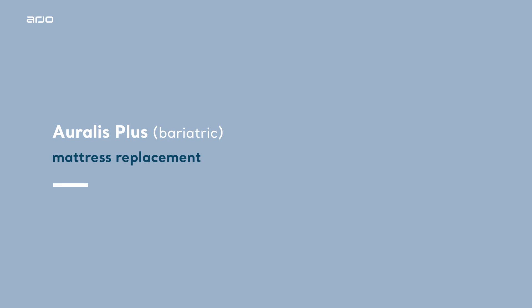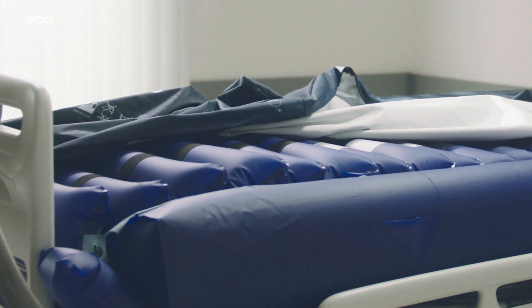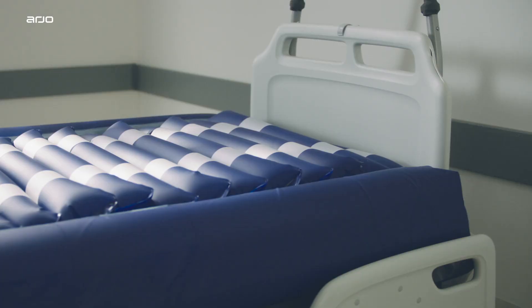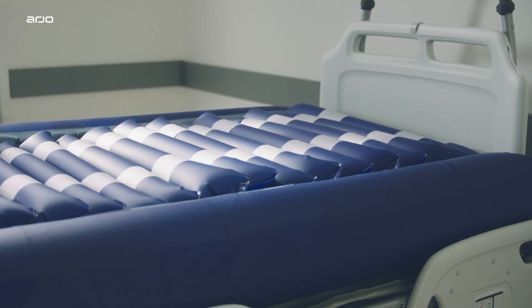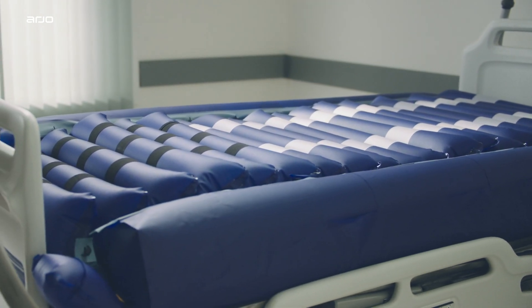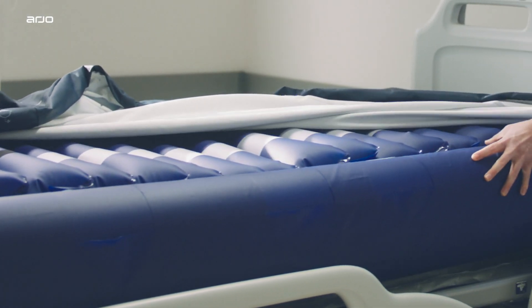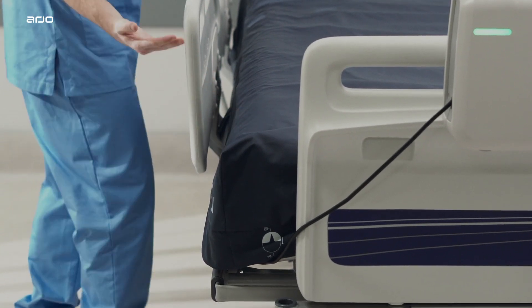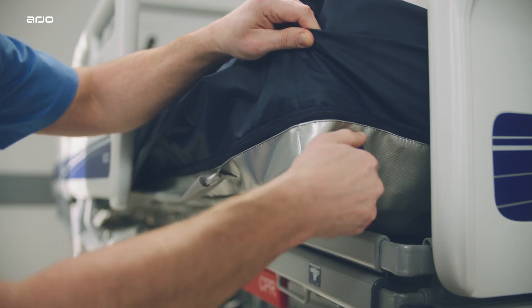Auralis Plus bariatric mattress replacement. The Auralis Plus mattress replacement system provides a width-adjustable support surface suitable for plus-sized patients weighing up to 454 kilograms or 1,000 pounds. It is of similar construction to the Auralis non-bariatric surface, with three-zone therapy: three head cells, 12 torso cells and six heel guard cells. An additional feature is on-demand mattress width adjustment driven by integrated air-filled side bolsters. Control valves at the foot end on either side enable adjustment of mattress width, creating a bariatric support surface suitable for access through doorways and elevators for efficient patient transfer.